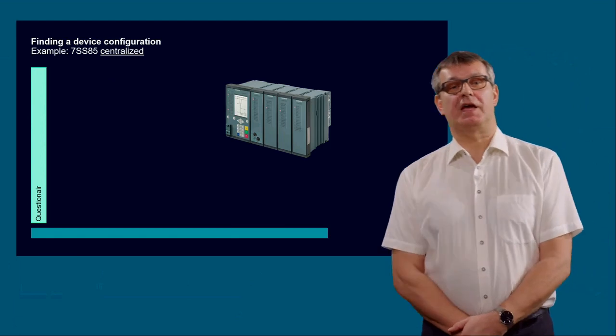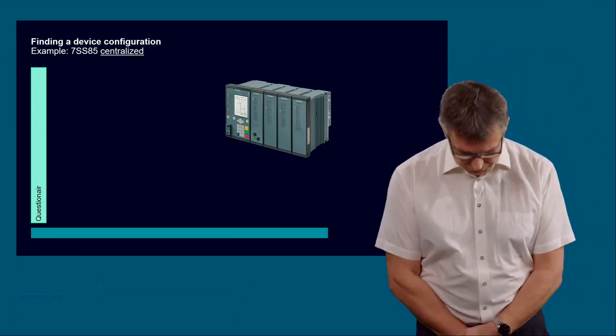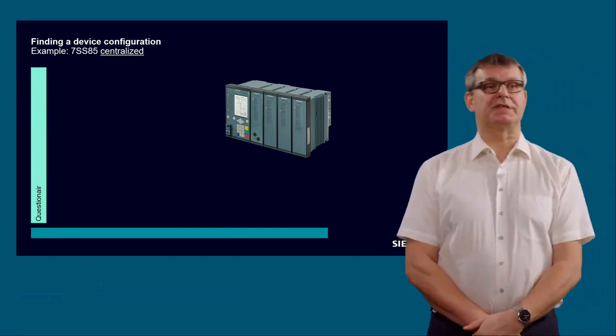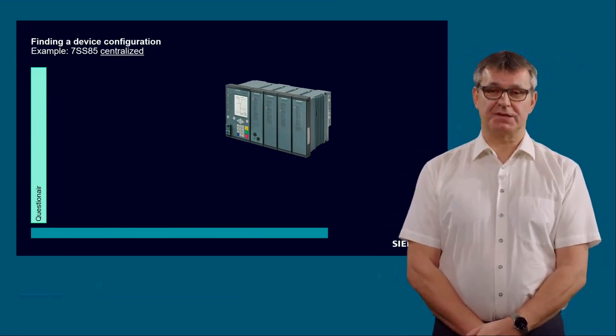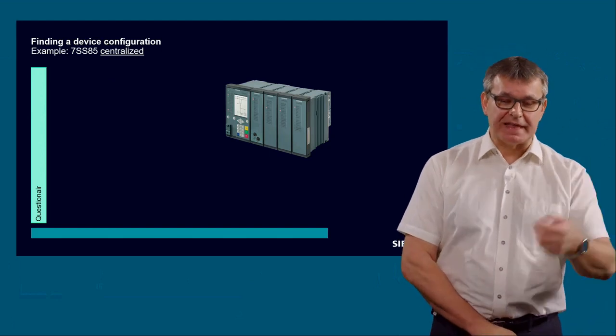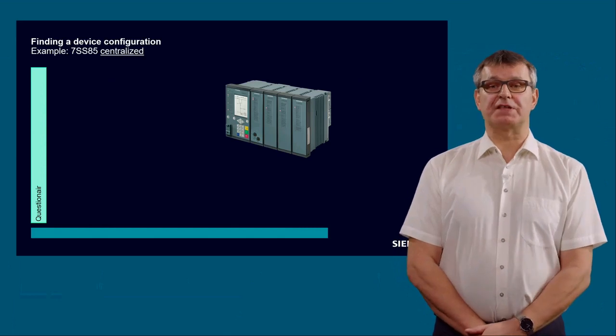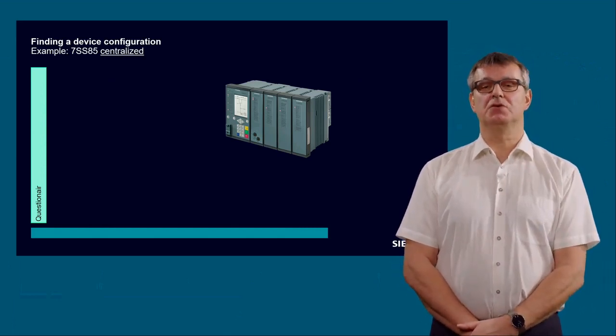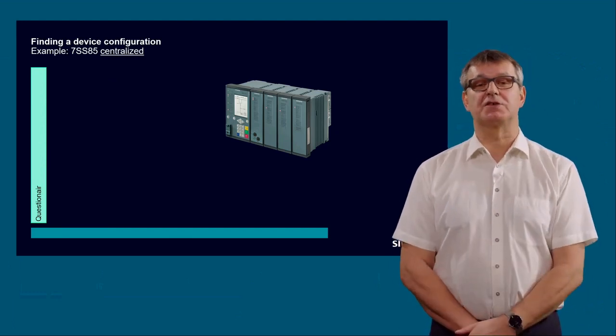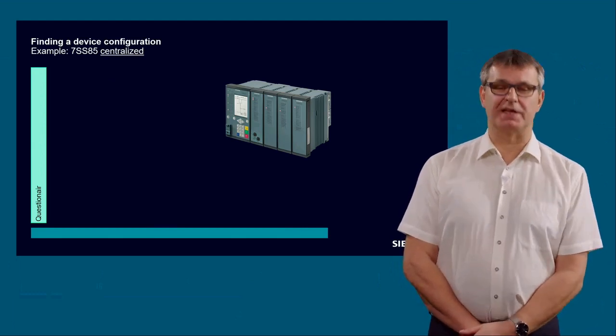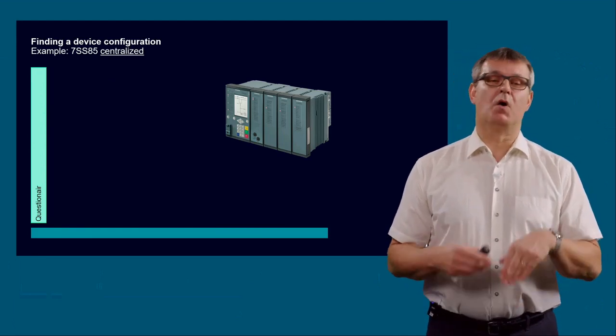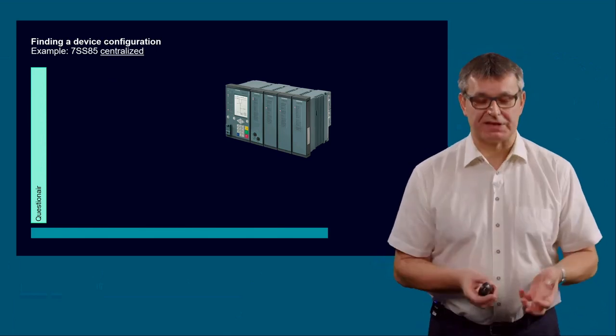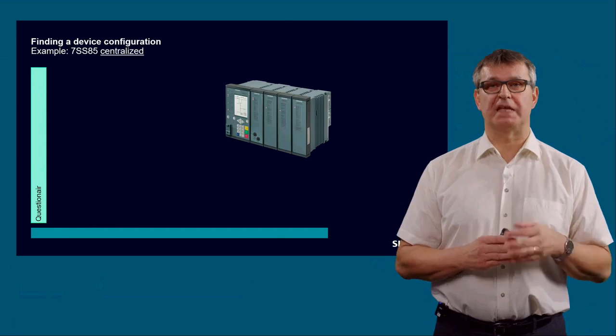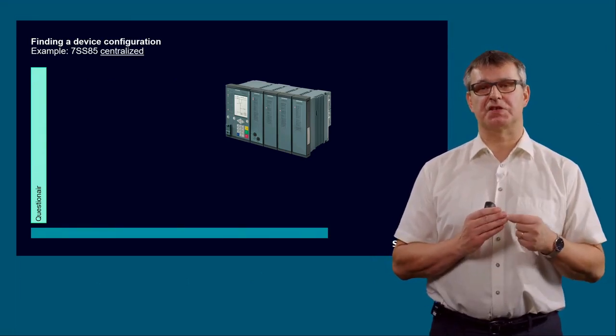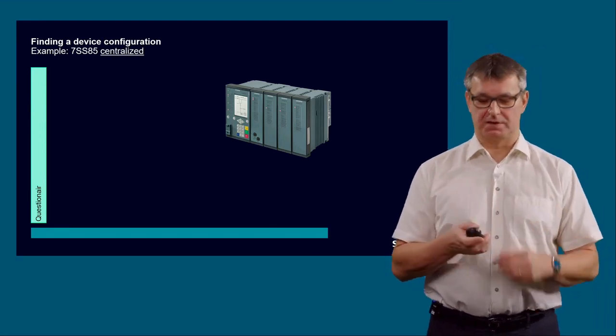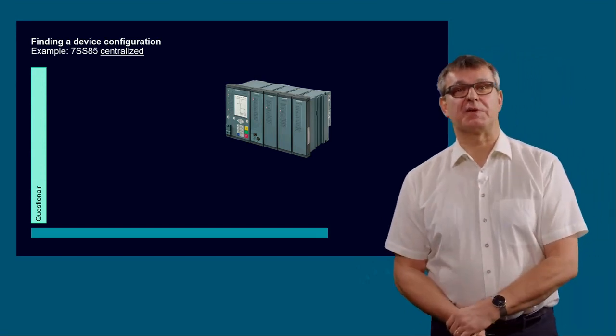Okay, finding a correct device configuration is split into 3 parts. First part, find a correct device configuration for the 7SS85 centralized bus bar protections. Next, of course, will be find the correct configuration for the 7SS85CU, and finally find, which is more or less a combination, the correct devices for the IEC 61850 compliant distributed solution. The most complicated, because the most things are new, will be the explanation of the centralized bus bar protection. But if you know the centralized bus bar protection and how to find the correct configuration for it, it will be quite easy to find the correct configuration for the other ones. So let's concentrate in the first step on the centralized bus bar protection.